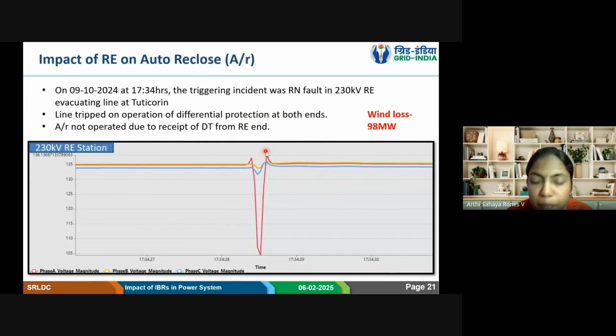So next is the impact of RE on auto recloser. I hope all of you are aware of auto recloser. In India, for the transmission system, and even in the distribution system at a few places, we have this three-phase group operated auto reclose. In our transmission system, it's mandatory from 220 kV and above lines. Auto recloser is mandatory because most of the faults in power systems are of transient type. 80-85%, as we study in the textbook, and it exactly matches with real time also. That's what we also observe. 85% will be single line to ground faults. That being the case, given a chance for the fault to get cleared, there are many chances that we can get back the line without losing reliability. So that is why we go for auto reclose.